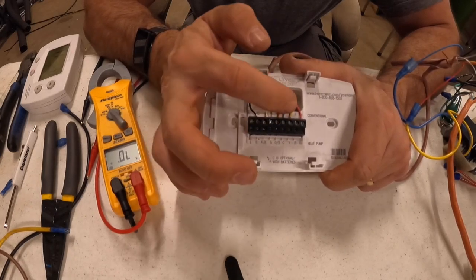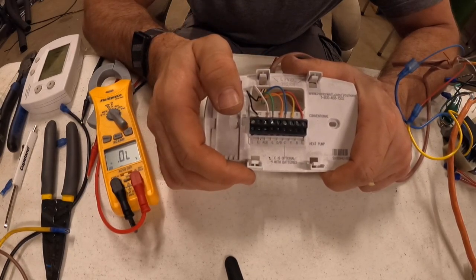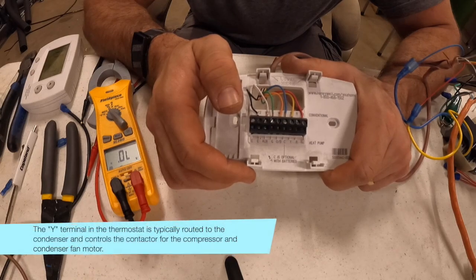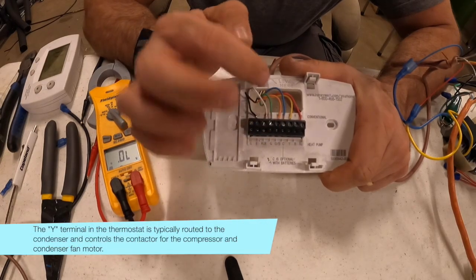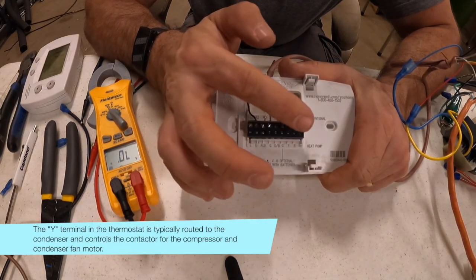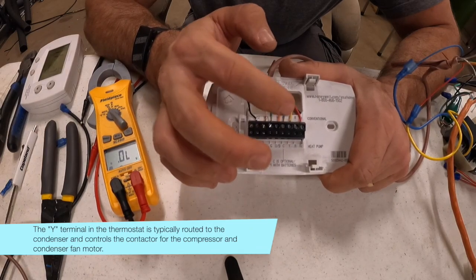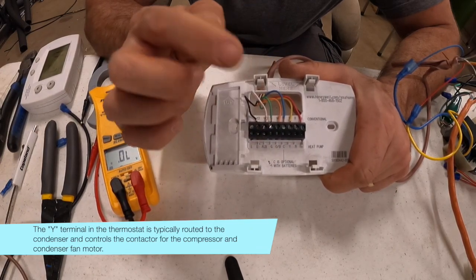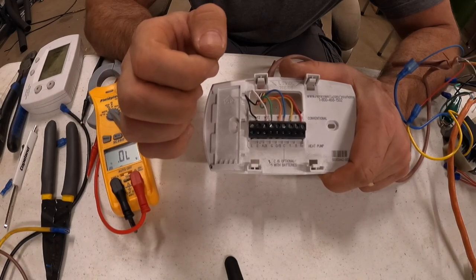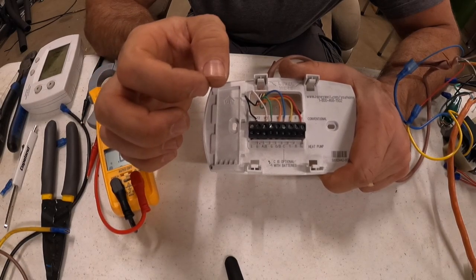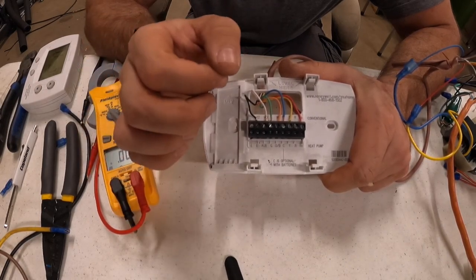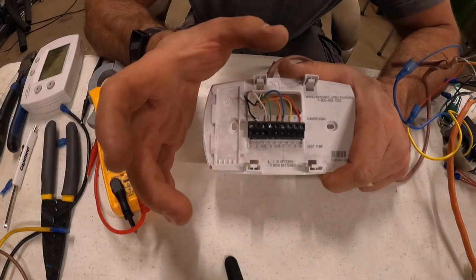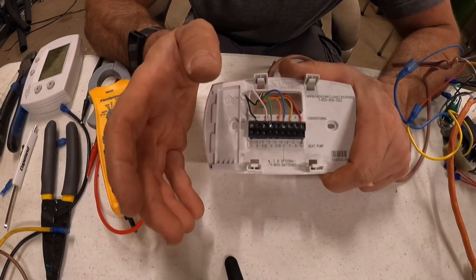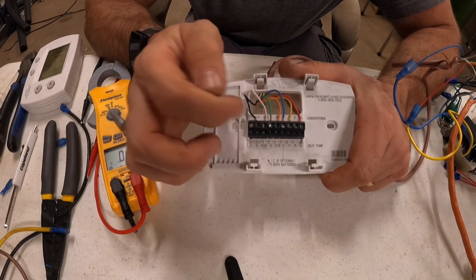Y is going to be yellow for this configuration. Y is the compressor contactor. So the thermostat, depending on what you're calling for, may send 24 volts to Y, which is going to go to the control side of your contactor. Well, we're going over a heat pump here, so it goes to the contactor on the outdoor unit or condensing unit to engage that.